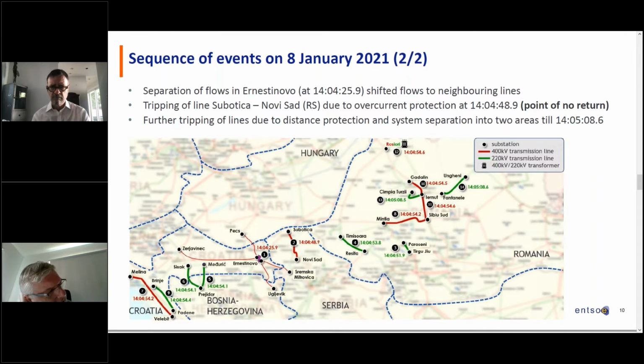And this led then to further disconnections of plenty of other lines, most of which were disconnected due to distance protections. Now, distance protections are protections that safeguard us from short circuit flows, so flows which are too high for the equipment, which have to be cut as quickly as possible. So all these lines, in a way, detected short circuits which were not really there, but I will come to that, because all this is a consequence of the loss of stability between the two areas. So all these lines afterwards, number 3, number 4, to the east, and then to the west, 5, 6, 7, in the east, in Romania, number 8, and then Croatia, number 9, and so on, 10, 11, 12, 13, 14 lines disconnecting, which effectively splits the grid into two parts.